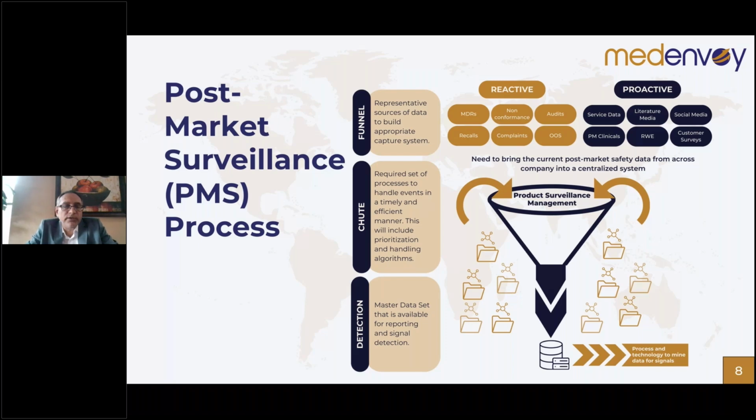So the data or information you are getting from literature, clinical literature, or a database or competent authority database, where a similar technology or similar device from your competitor or someone else has experienced something. It hasn't happened to your product yet, but you're proactively assessing if it is applicable to you and taking appropriate action. So there are proactive elements and reactive elements, and then we take both sets of inputs, and it goes through your analysis, data collection, and at the end, as a process output, you should have a formal report.